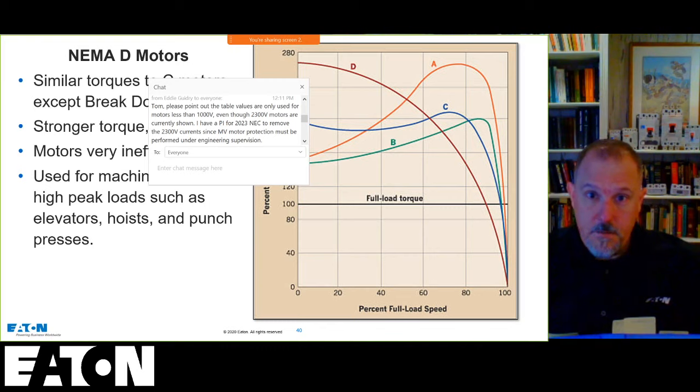I'm just looking to see if there's any part. Yeah, so Part IV. So here it is. Part IV shall not apply to motor circuits rated over 1,000 volts nominal. So it tells you right at the beginning of that part. So even though you're at 430, whatever, always go up to the parent text. So if you're at 430.52(C)(5), go look at what 430.52(C) applies to, and then understand what 430.52 applies to, and then take a look at what part it's in, and understand what that applies to, to really understand each section of the code and its requirement. So that's a good point, Eddie. Thanks for pointing that out.